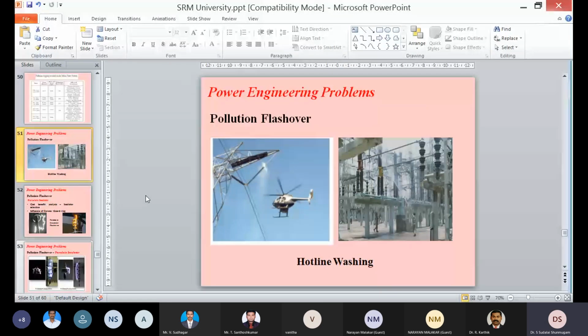So how we encountered this pollution flashover? Excuse me, sir, is the PPT visible to you, sir? Viewable. Fine, sir. Thank you. So how we encountered the pollution flashover is we started hotline washing in northern India, but that was quite a failure. We even tried to clean the substation insulators by means of high jet washing, but again, it doesn't provide optimal result. Finally, we moved to insulation selection itself, where we select appropriate insulation to avoid pollution flashover due to high contaminant environment.